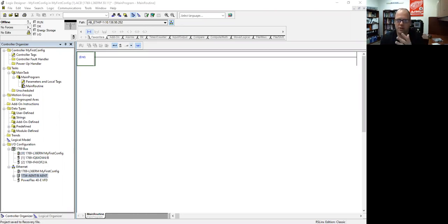An add-on instruction is very much like that, in the sense that if I always have the same set of inputs or variables that I use and the same set of outputs that I can control, but they may be different around the plant, I can set up a standardized set of code that says, here's all the inputs I need to assign, here's all the outputs I need to assign, and now execute. The downside of add-on instructions is you can't change them online, but you can utilize them multiple times. So I want to demonstrate a very simple way of going about it.